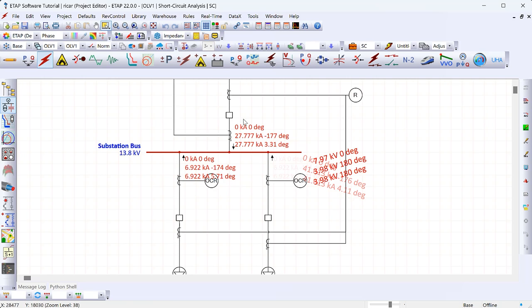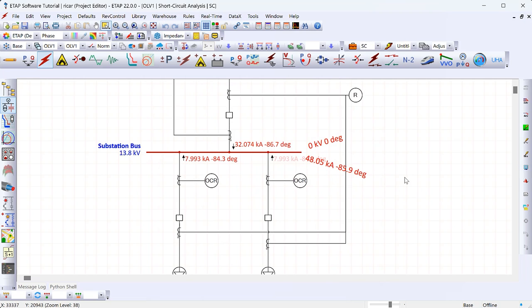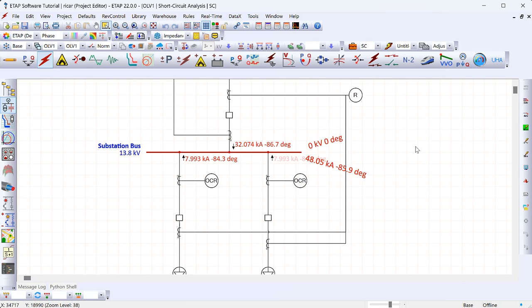Clicking OK, you can now see all individual phase values. For example, for a B-to-C line-to-line fault, the contribution from the transformer would be 0 kA for the A phase and 27.8 kA for both B and C phases. If you want to see the maximum fault current level, that's typically a three-phase fault — select 'Max Short Circuit' so all transients are taken into account.